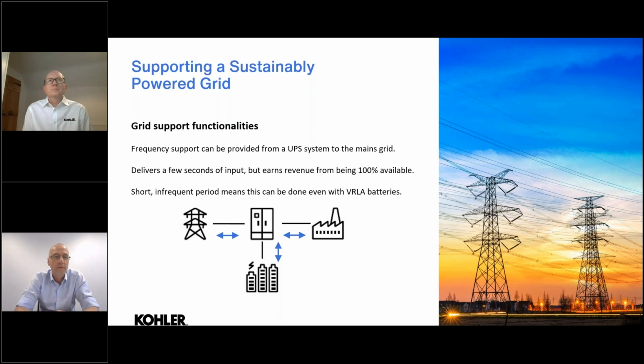So as Ian mentioned, frequency support can be provided from the UPS systems to help the mains grid. And there are different ways of doing the frequency support, as we know. Some of them are to backfeed the grid, some are behind the meter functionalities. But having that ability to deliver maybe just a few seconds of supply from frequency support can earn large money when you're available 100% of the time. And if you're doing it for short infrequent periods, this means it can be done even with the VRLA batteries, rather than having to go towards a cyclic lithium battery.